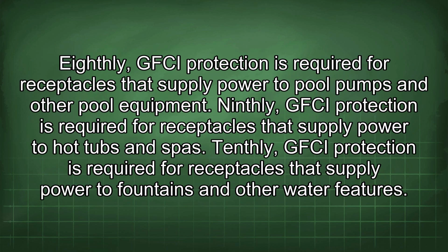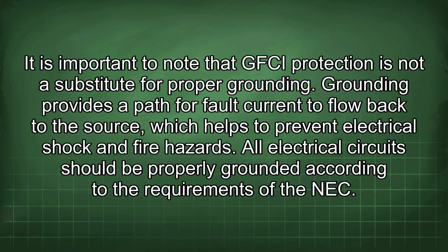Eighthly, GFCI protection is required for receptacles that supply power to pool pumps and other pool equipment. Ninthly, GFCI protection is required for receptacles that supply power to hot tubs and spas. Tenthly, GFCI protection is required for receptacles that supply power to fountains and other water features. It is important to note that GFCI protection is not a substitute for proper grounding.